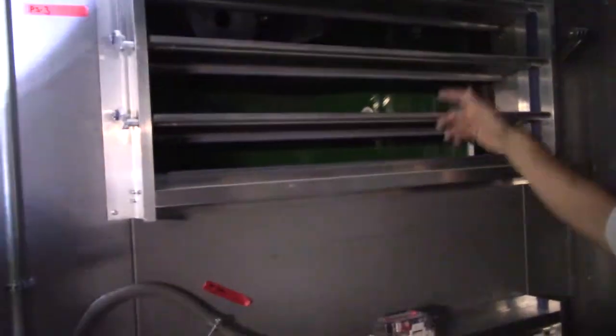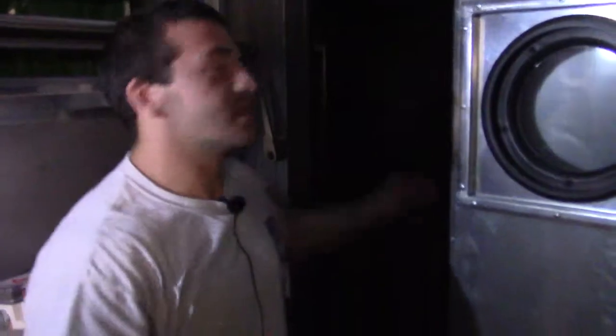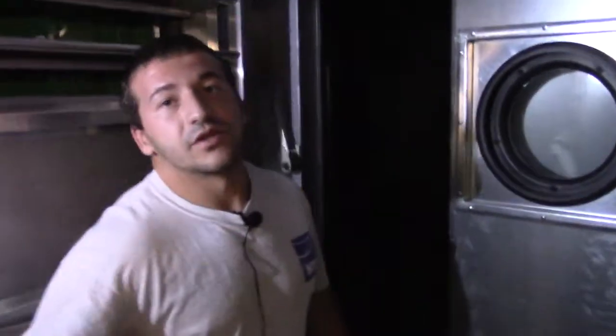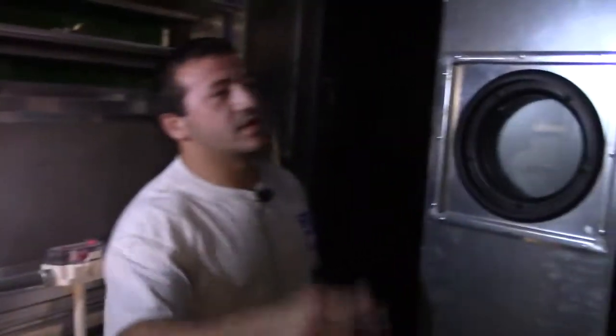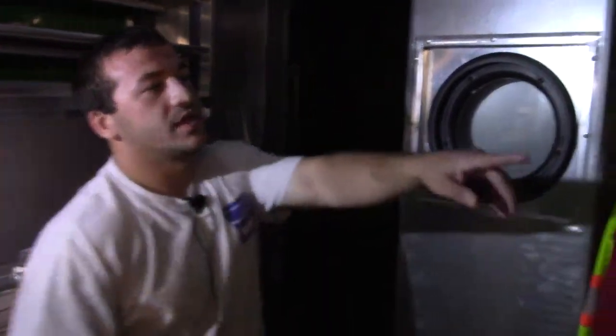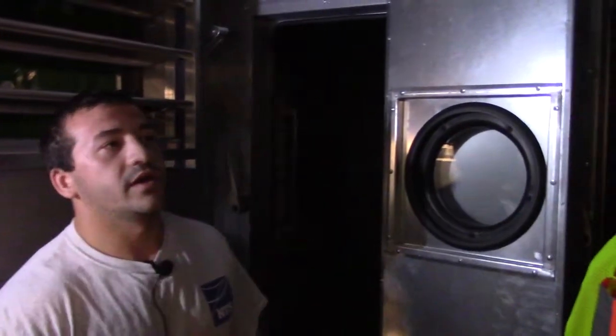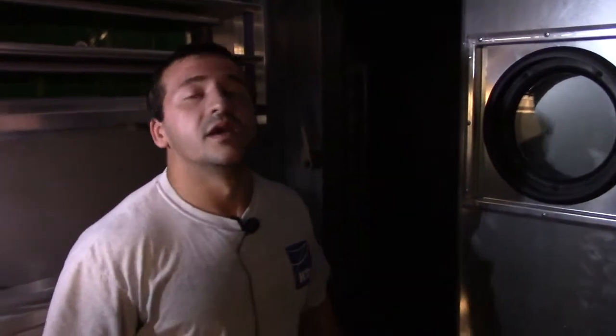Can you do that one more time so I can try and grab it on the video? Sorry. These right here are the gravity dampers for the fan. As the fan runs and shuts down, they'll blow open if they're closed. The unit is basically 2 sections. The section on the opposite side of these doors is your supply air section, and this is your return and exhaust air. The only time the air is cross stream is through the heat wheel. If the heat wheel ever gets dirty, to clean it you'd want to blow it out with nitrogen from one side and put a shop vac on the other side to suck up all the dust. You don't want to hit it with any more than 100 psi.